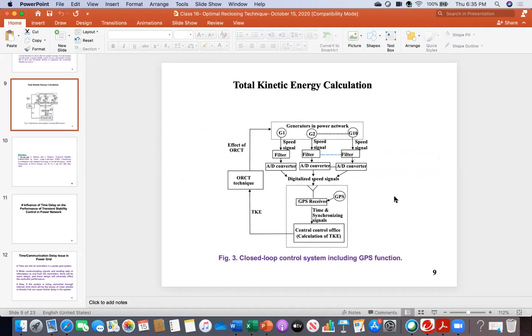Clearly, if you have a thyristor device, it has a firing angle, and that firing angle is itself a delay. Similarly, there is the AVR-governor system, the automatic voltage regulator governor system, power system stabilizers, and voltage regulators. And as we just discussed, circuit breakers introduce some delay too, since a circuit breaker needs time to open and we have to allow time for it to reclose.